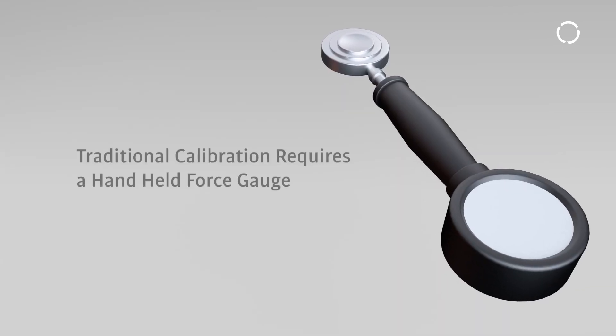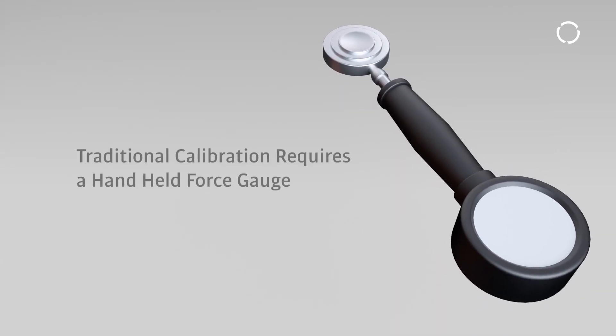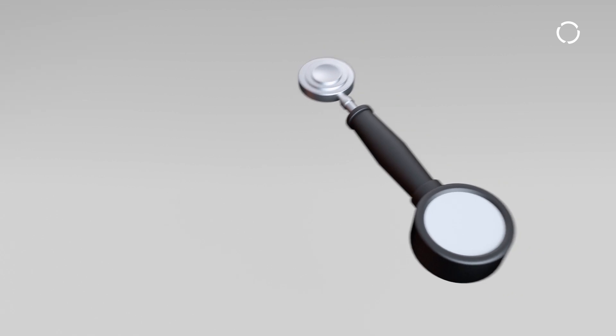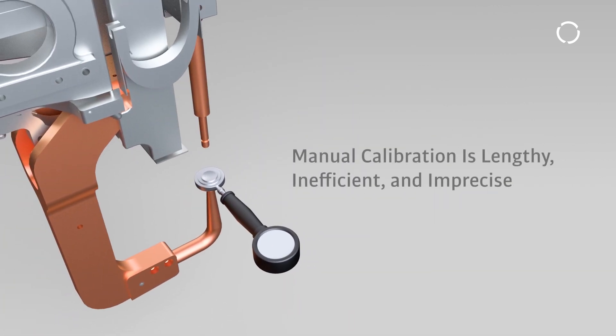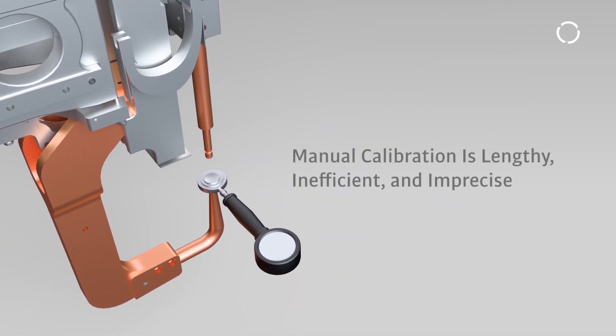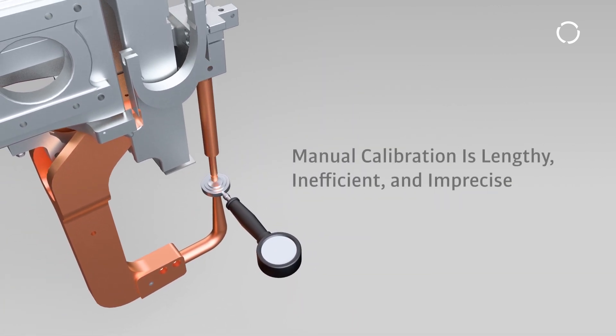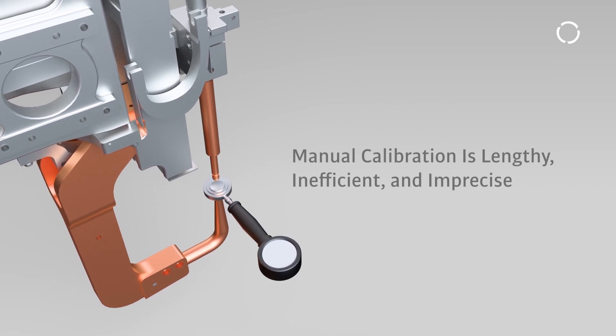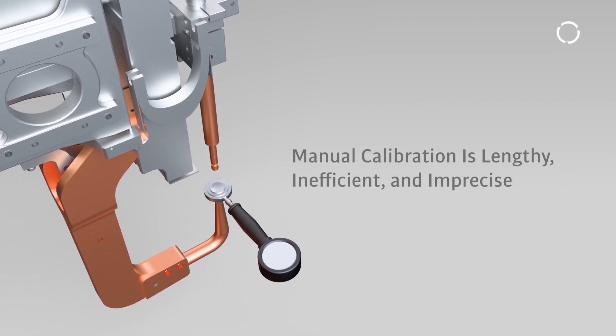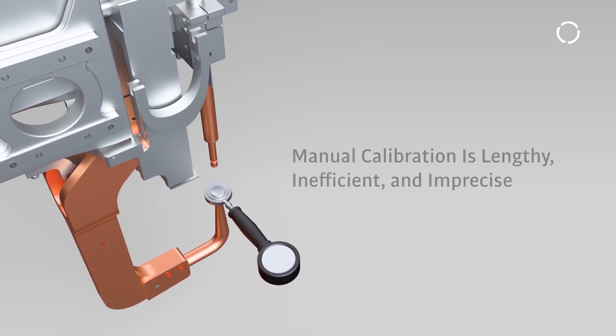Traditional gun calibration requires a handheld force gauge and an iterative process in which a technician must close the gun in a slow, safe speed on the gauge, document the force, then enter it into software to generate a calibration curve.